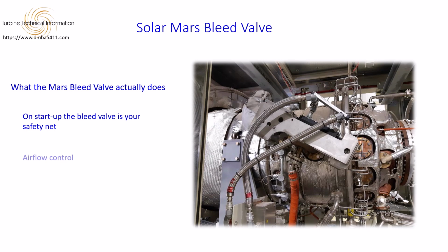In the early part of the start sequence, the front stages of the compressor are already moving a lot of air. The back stages are still inefficient. They can't process all that flow. If you don't get rid of the excess, the compressor will surge. And when a Mars surges, it doesn't cough, it hits hard. You're into blade and seal damage, and a very expensive repair. So during start, the bleed valve is not optional, it's the life support for the compressor.